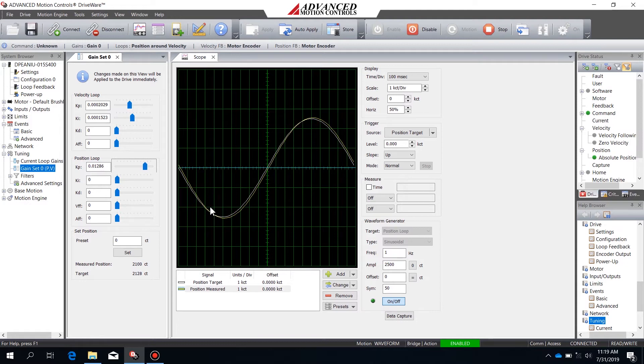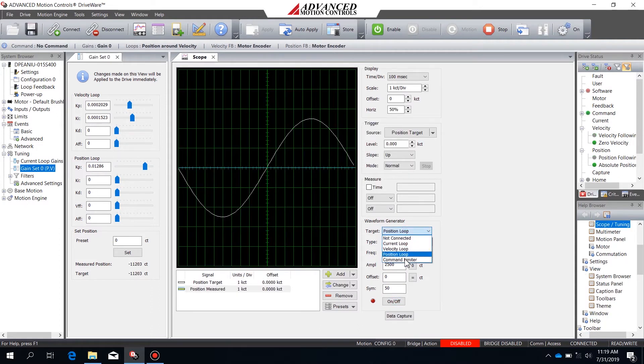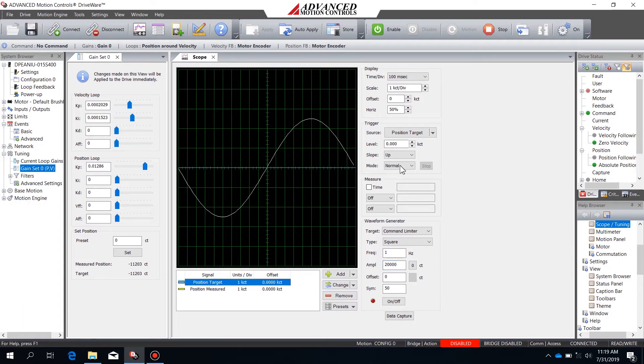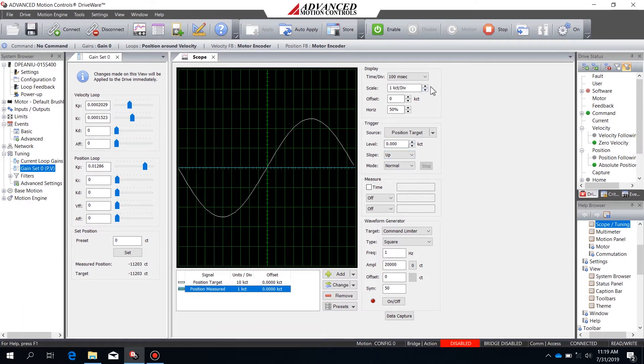At this point the error has gotten pretty small, so I'm done with sinusoidal-based tuning and moving on to waveform-based tuning of a command profile. I'll open up the command limiter, change the type to square wave, and set the offset to zero. My amplitude will be the size of my motion profile, using the velocity and acceleration set before. I'll also need to readjust the scaling so everything's visible on the scope, and reduce the frequency so there's some time where the machine is not moving, ensuring stability at zero velocity.